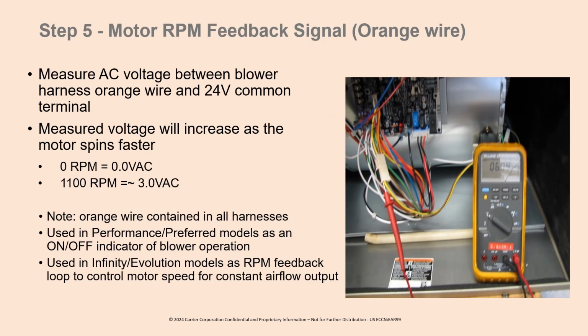So now let's check the motor RPM feedback signal on the orange wire. You will be measuring AC voltage between the blower harness orange wire and the 24-volt common terminal on the control board. Measured voltage will increase as the motor spins faster. So at 0 RPM, you should have 0 volts. At 1100 RPM, you should have 3.0 volts.